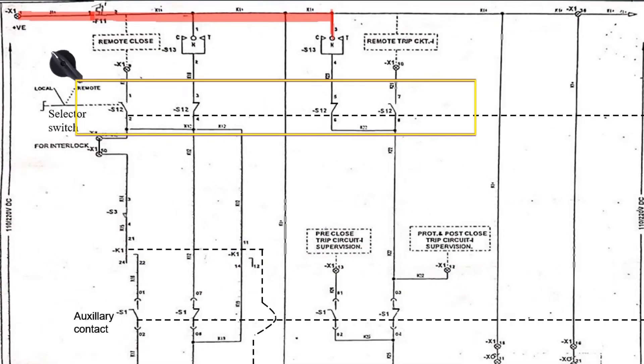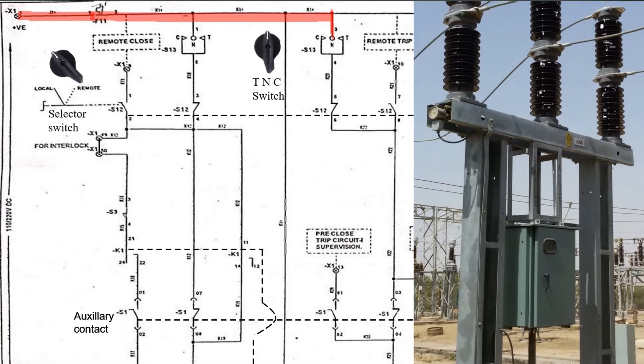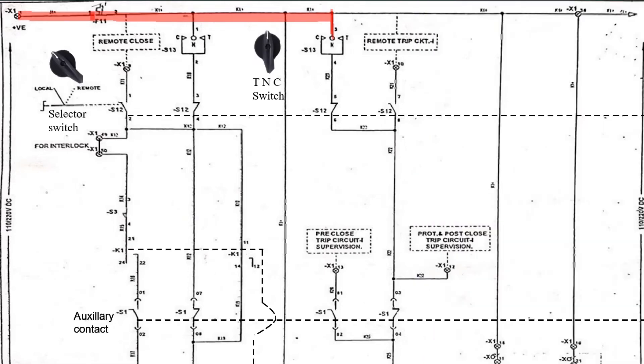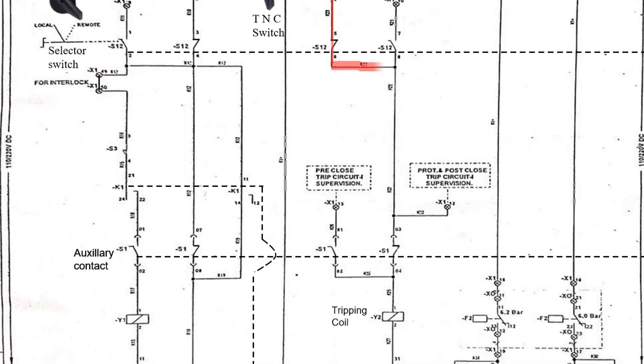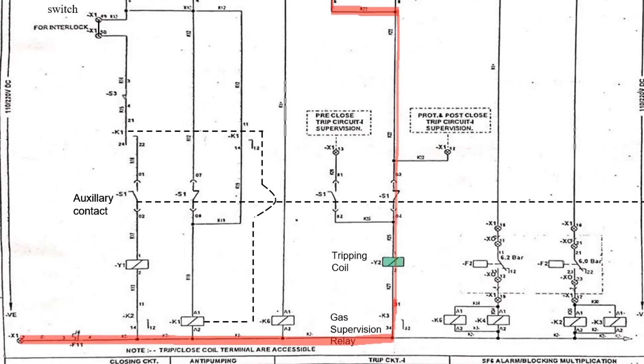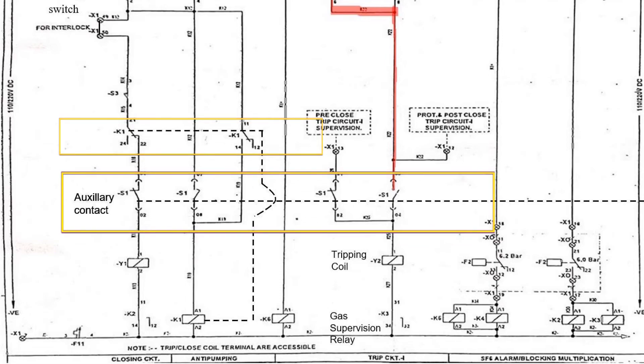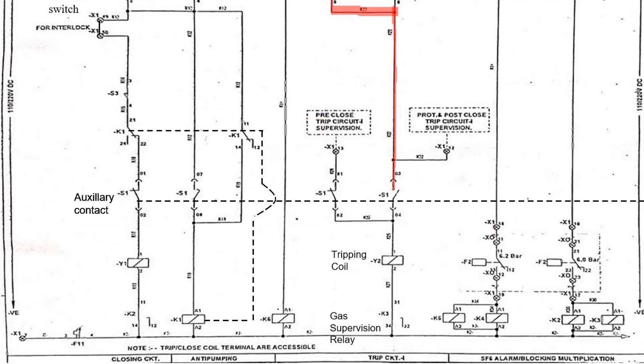Now again, as we have seen in our previous videos, we will follow the same logic. In local mode, the selector switch is connected to local mode, and when the operator performs the trip operation from where the circuit breaker is placed in the switch yard, the current flows like this, passing through the tripping coil, gas supervision relay and fuse, completing the trip circuit. As soon as the trip circuit gets completed, the tripping coil energizes, and as soon as the circuit breaker gets tripped, its auxiliary contact S1 along with the anti-pumping relay K1 changes its contact — NO becomes closed and NC becomes open. Also, the tripping coil gets de-energized. So with this, it completes the trip circuit in both local and remote mode.